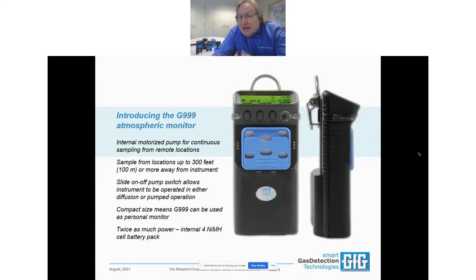You don't have to have a pump. If what you want is an instrument that runs twice as long with the same set of sensors as the G888, leave the pump turned off, or leave the pump entirely out. You can sample with the pump up to 300 feet or 100 meters or more away from the instrument.